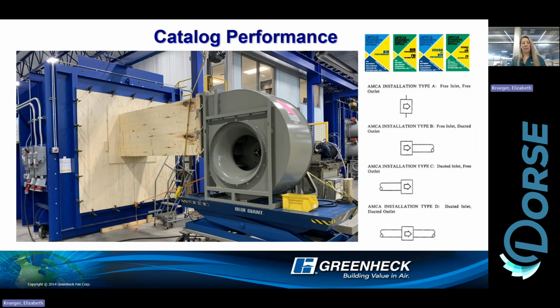This fan, if you didn't know, AMCA testing requires you to test the fans every 3 years. So we are constantly testing fans on our air chambers. This setup in particular, like I said, is ideal, so we are going to get the best performance possible. We're going to test it here in our facility. The same fan gets sent down to Chicago and gets tested by AMCA and verified there.